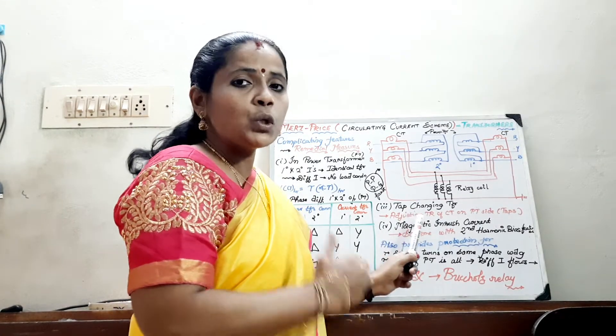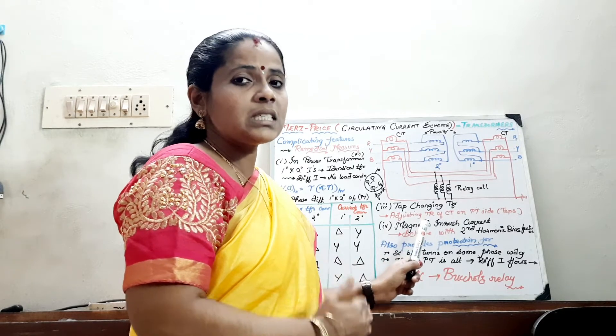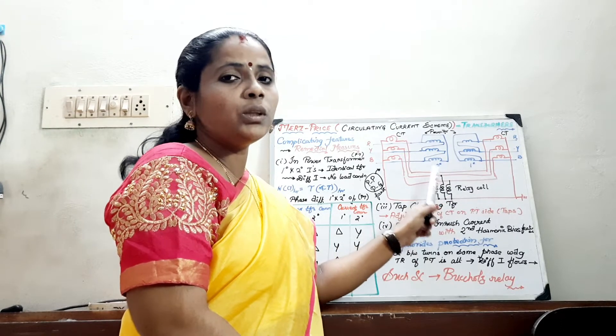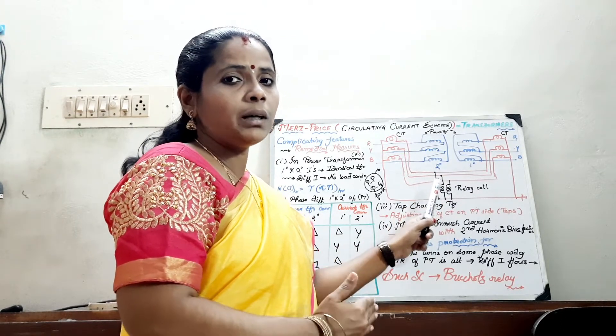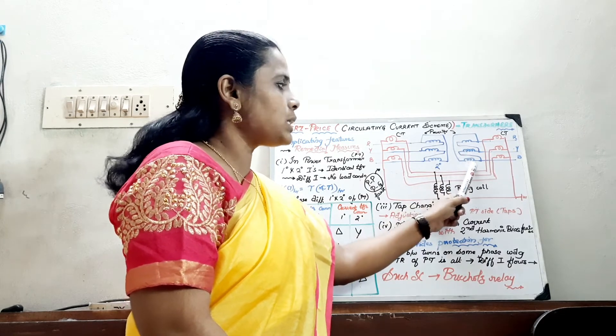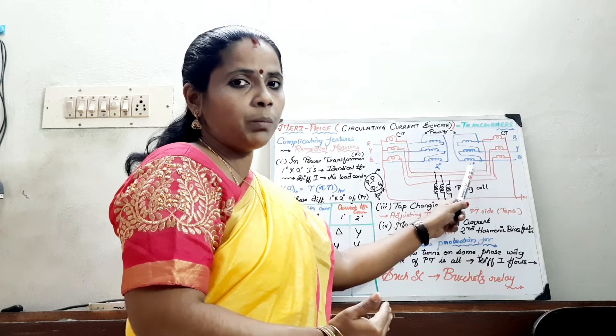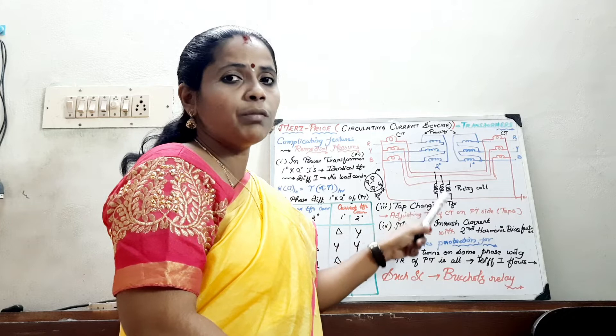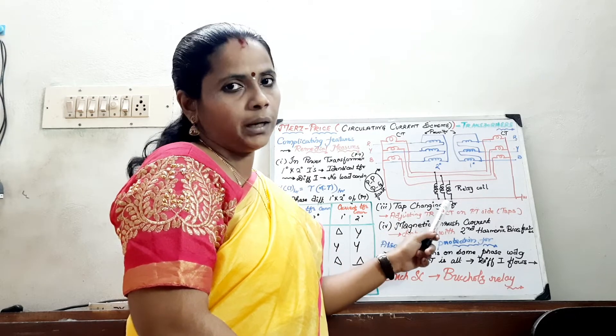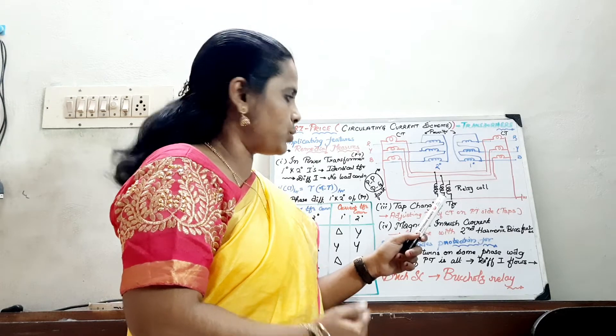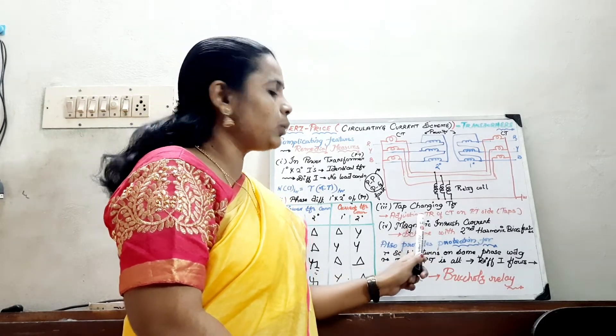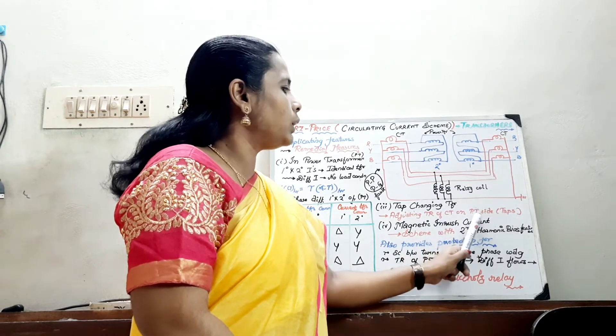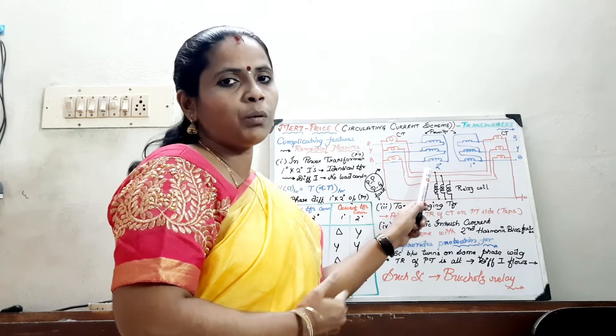The third problem: transformers often have a tap-changing feature, where either the primary or the secondary is provided with taps. Under normal conditions, this tap changing will create a differential current that flows through the relay, causing the relay to mal-operate. This should not occur in the circuitry. This tap-changing problem can be overcome by adjusting the turns ratio of the CT on the particular power transformer side on which the taps are provided.